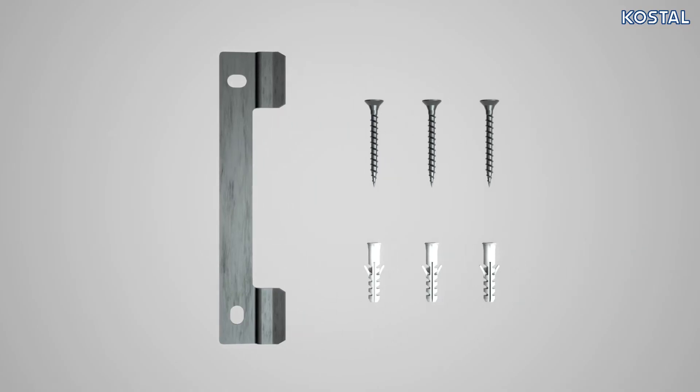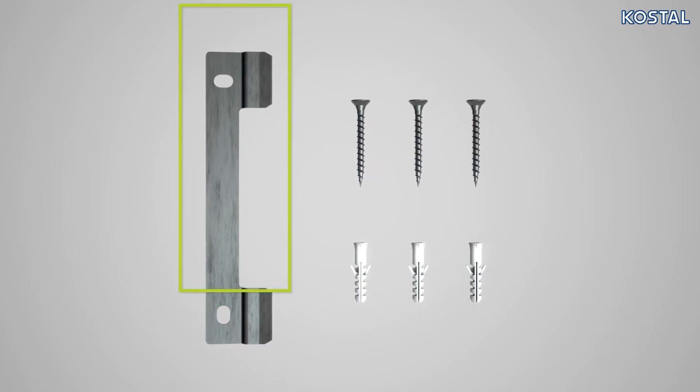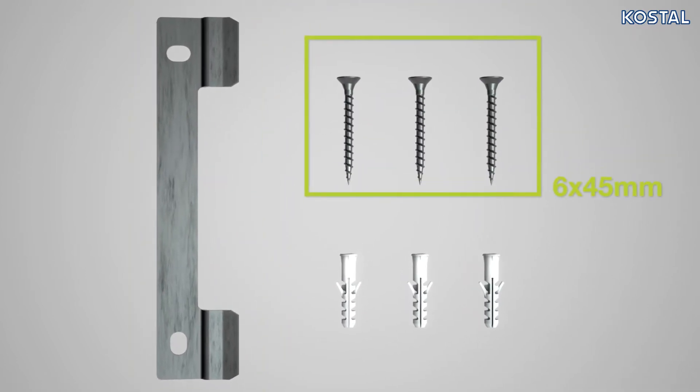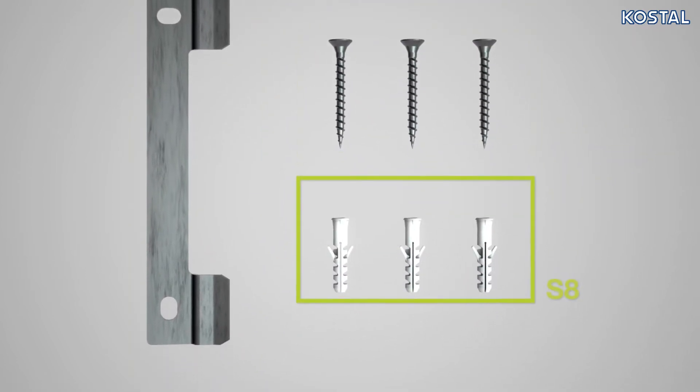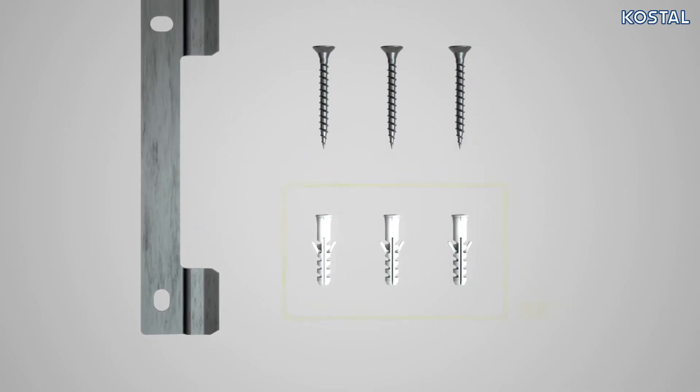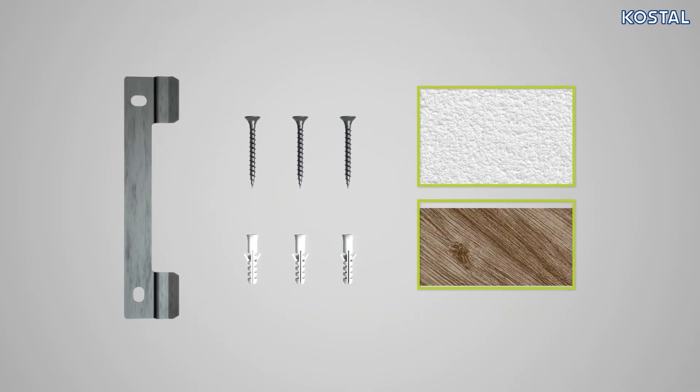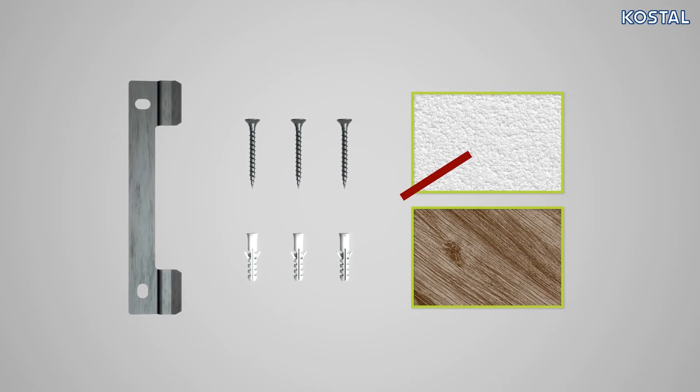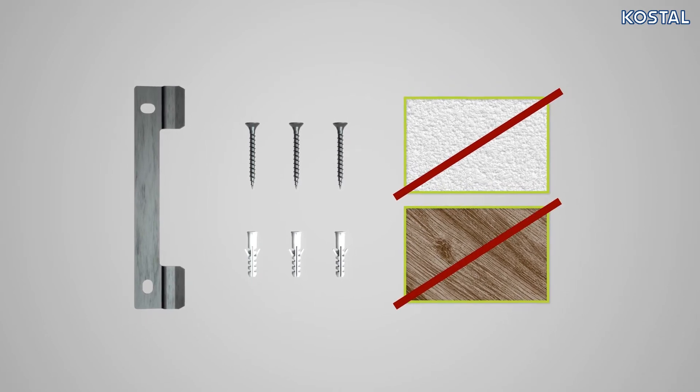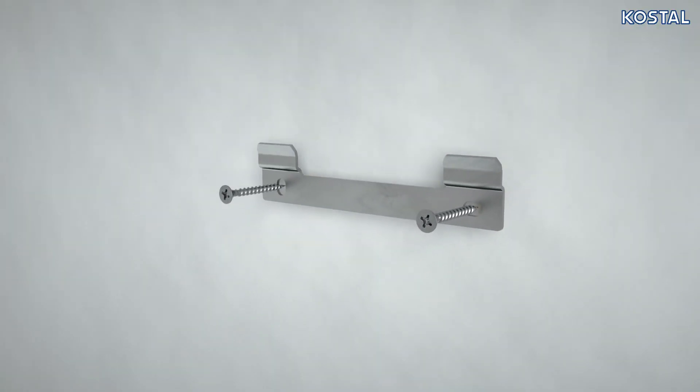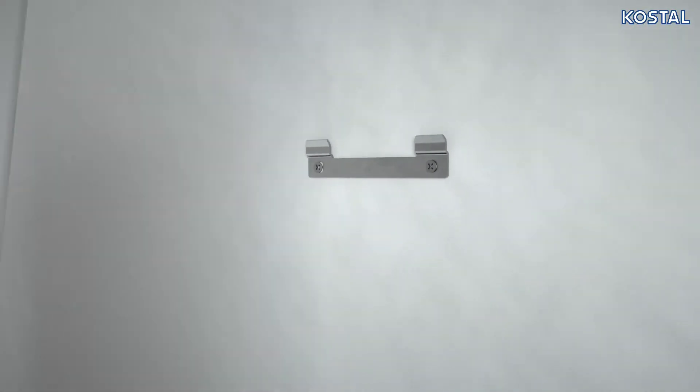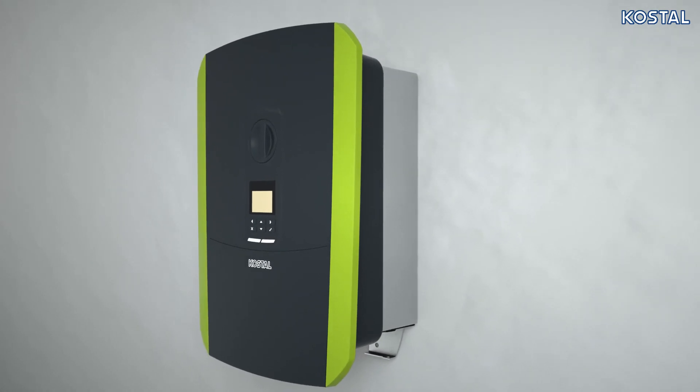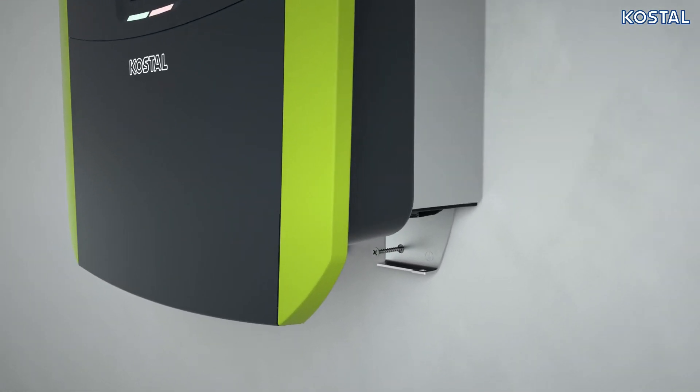The inverter is mounted on the wall using a mounting rail and three 6x45 screws and S8 screw anchors. Never mount the PlentiCore BI on a drywall or timber base. Attach the wall mount to a secure mounting face. Fit the PlentiCore BI in the mounting rail and also fix the device with a screw at the intended point.